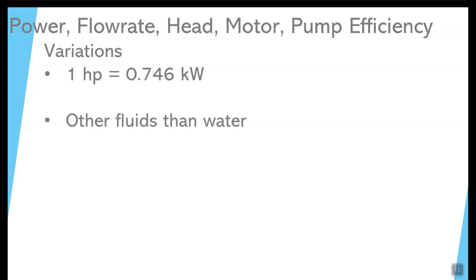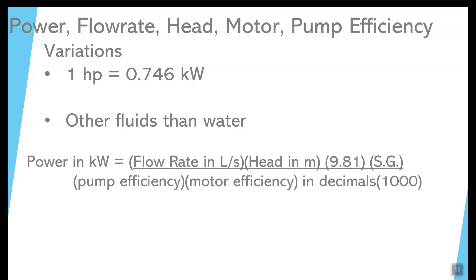What if you have fluids other than water? You can put the specific gravity into the formula. For water, specific gravity is one, so we don't have to worry about it. But if it's something less dense than water, like gasoline, you need fewer kilowatts. If it's more dense, like glycerol or a heavy slurry, the specific gravity is greater than one and you'll need more power.